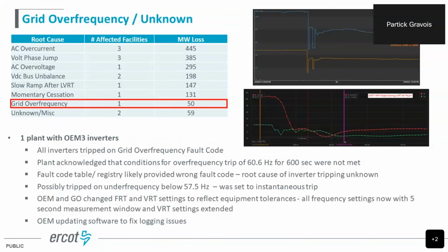Next, we have a grid over frequency, but we think this was probably a wrong fault code because the conditions for the overfrequency of 60.6 hertz for 600 sec were not met. And the generator owner realized that. So they found out it was likely some kind of fault code registry mapping that was incorrect. So the actual root cause of this inverter tripping is unknown. Again, this is the OEM3 that's out of business. So we have been working with the company that took over those service contracts.